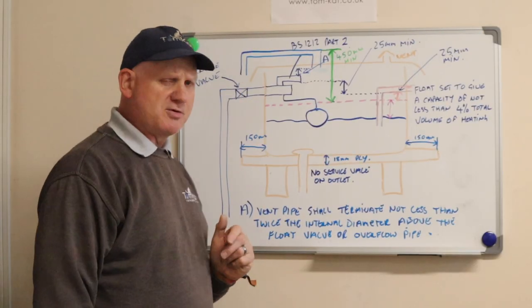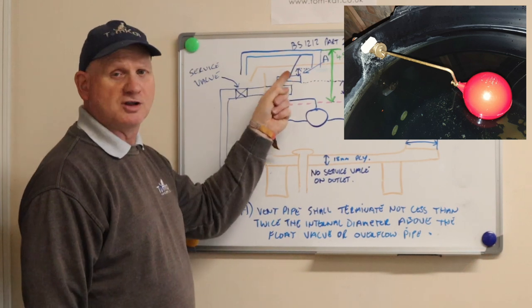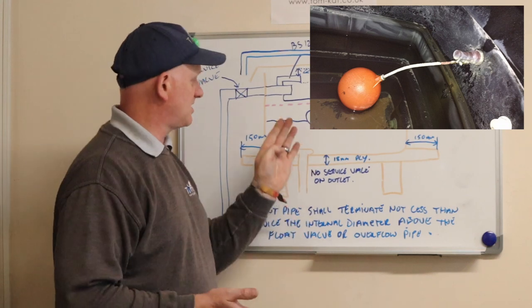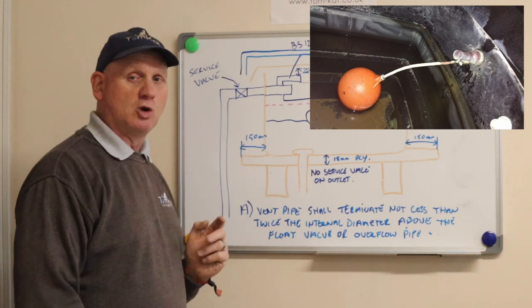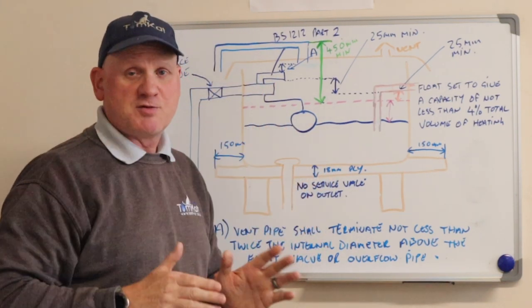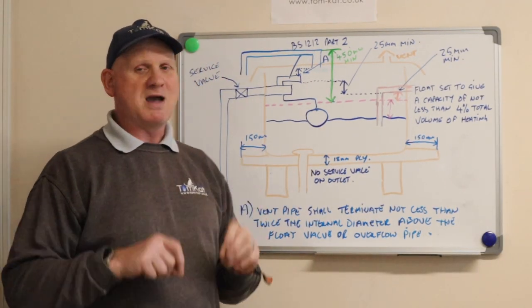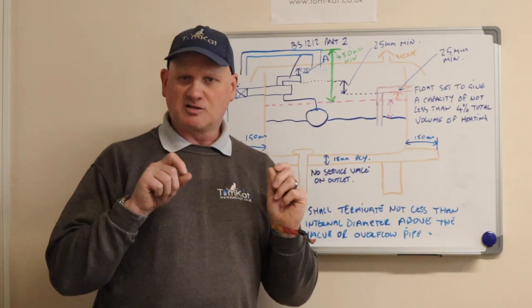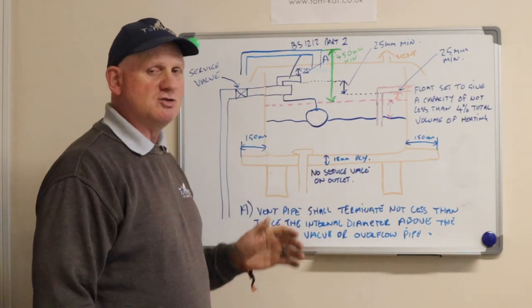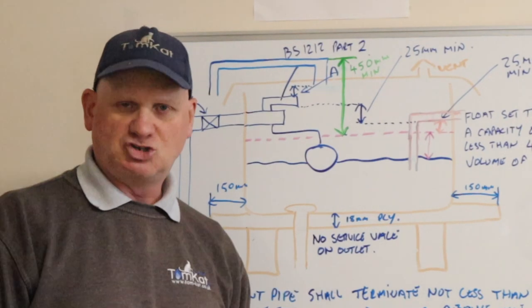For the float operated valve, we need a BS1212 part 2, which means water comes out from the top of the valve, not the bottom. A part 1 valve discharges from the bottom and in certain circumstances could allow back-siphonage of central heating water back into the cold water. You also need a minimum height of 450 millimetres above the system at the float valve end, to allow room to service it. Central heating water in a domestic premises is classed under water regulations as fluid category 3, and in a commercial installation as fluid category 4. That's why we use air gaps - you can't use double check valves; it has to be done with air gaps.